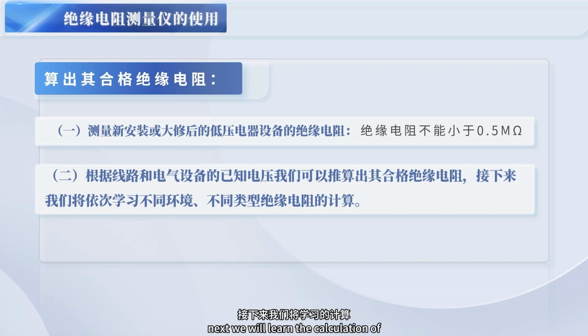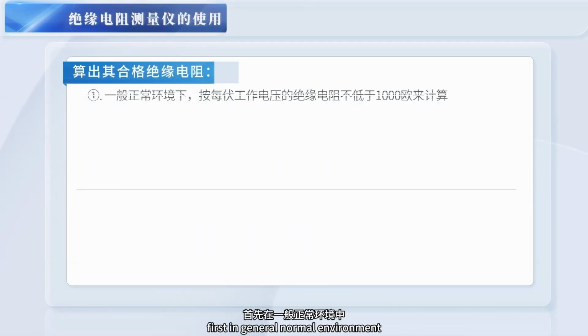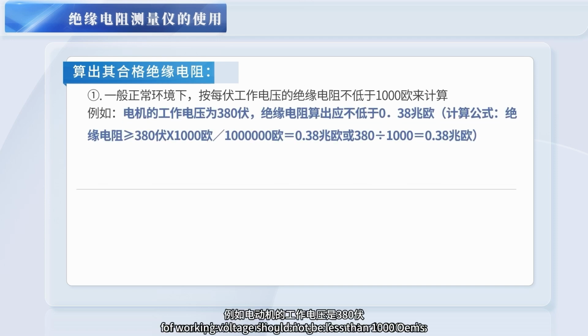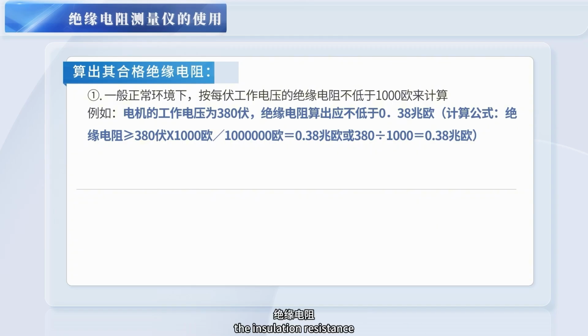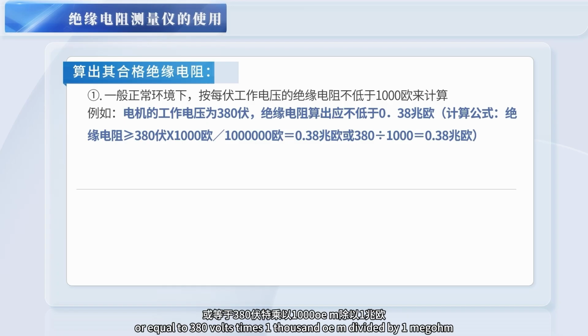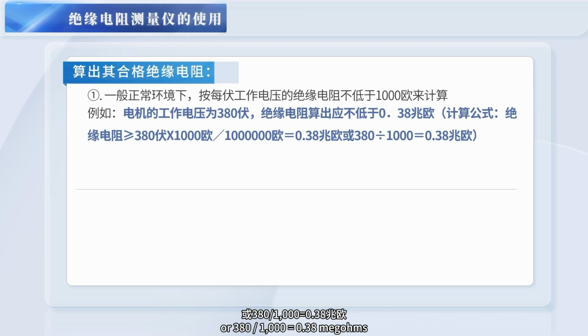Next we will learn the calculation of insulation resistance for different types of equipment in different environments. First, in a general, normal environment, the insulation resistance per volt of working voltage should not be less than 1000 ohms. For example, the working voltage of a motor is 380 volts. The insulation resistance should not be less than 0.38 megohms. The formula is insulation resistance greater than or equal to 380 volts times 1000 ohms divided by 1 megohm, which is 0.38 megohms.